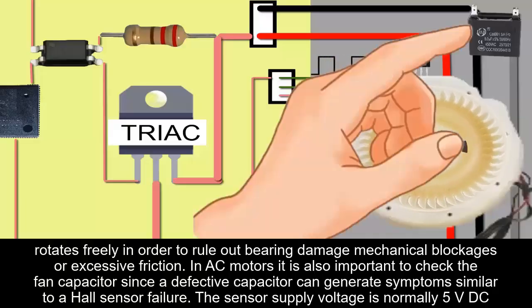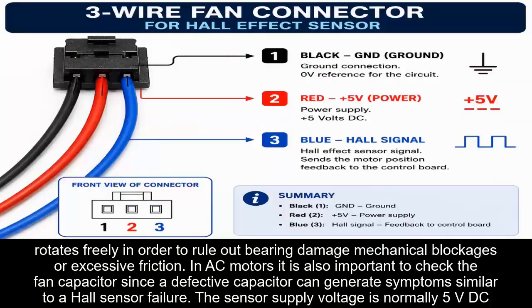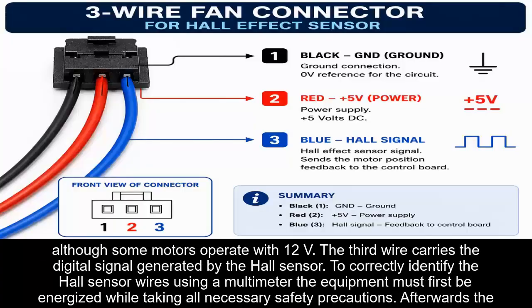In AC motors, it is also important to check the fan capacitor, since a defective capacitor can generate symptoms similar to a Hall sensor failure. The sensor supply voltage is normally 5 volts DC, although some motors operate with 12 volts. The third wire carries the digital signal generated by the Hall sensor.